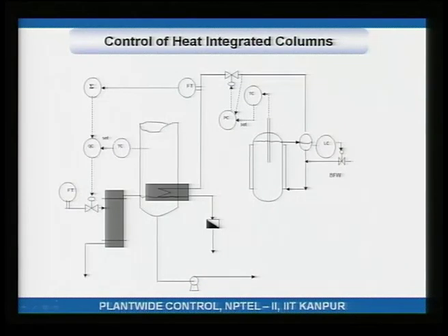And the way around it that we discussed last time was that instead of controlling the temperature using the auxiliary steam, what one should be doing is, let us see, this summation had to have another signal. Yeah, that is this signal. Steam from the reactor and steam from the auxiliary, this signal. You sum it up. So instead of manipulating the steam flow to the auxiliary reboiler, if you manipulate the total steam flowing, so this sum is giving the total steam, which is the steam from the reaction section as well as the steam to the auxiliary reboiler.